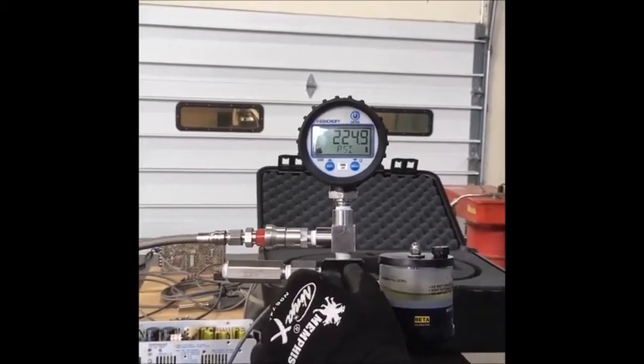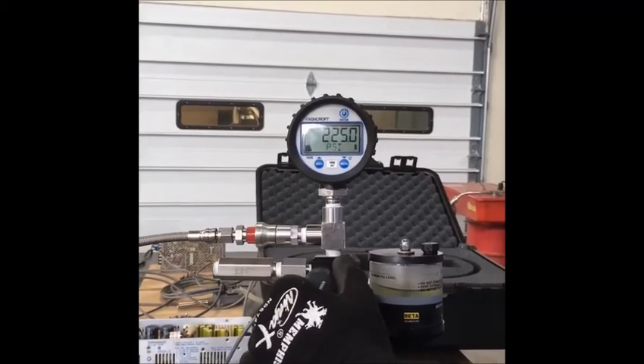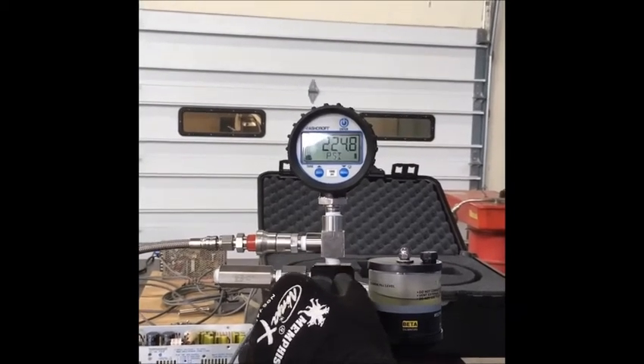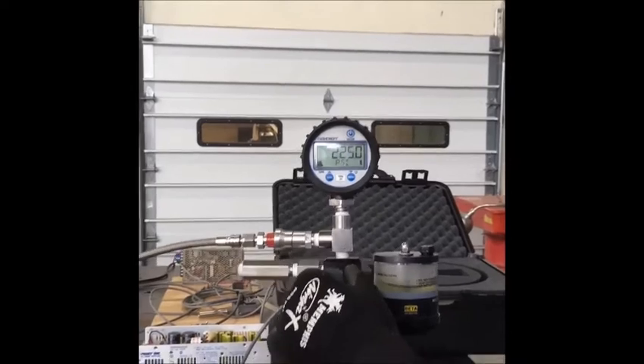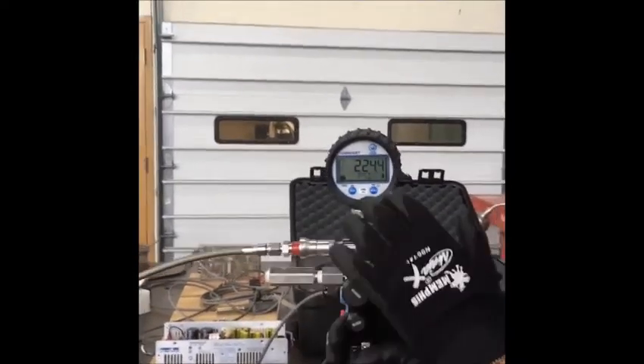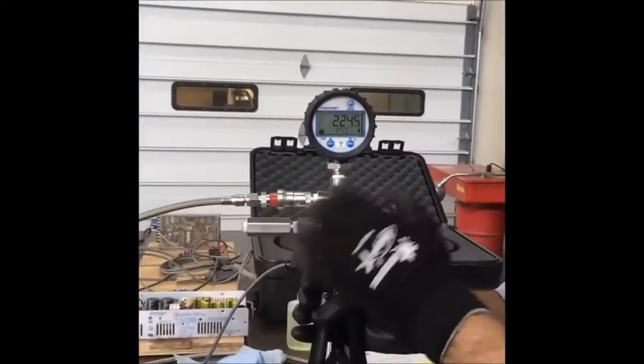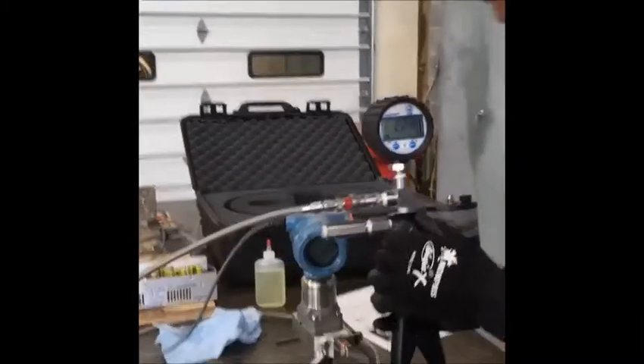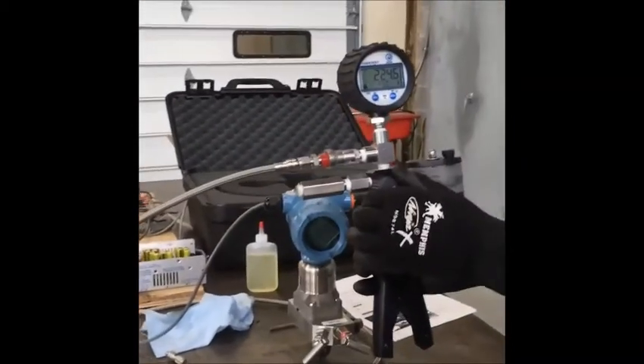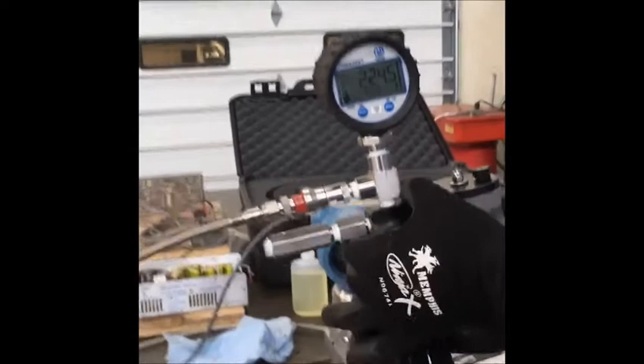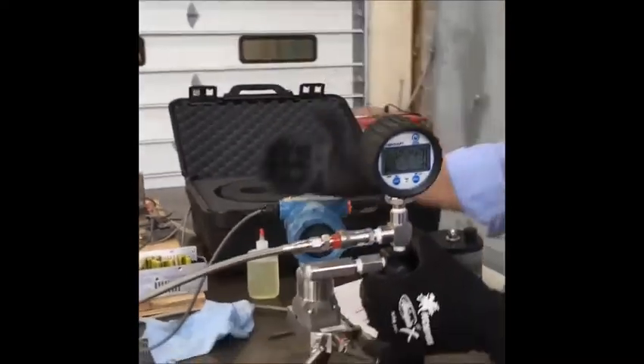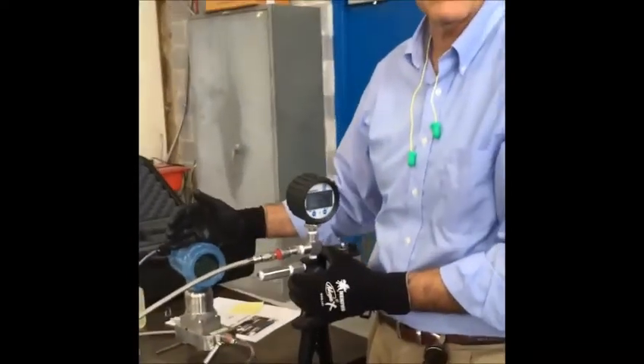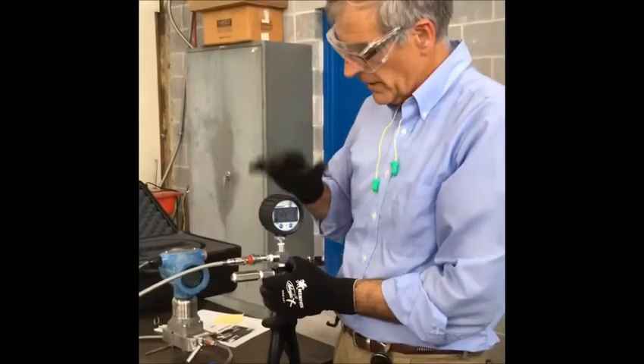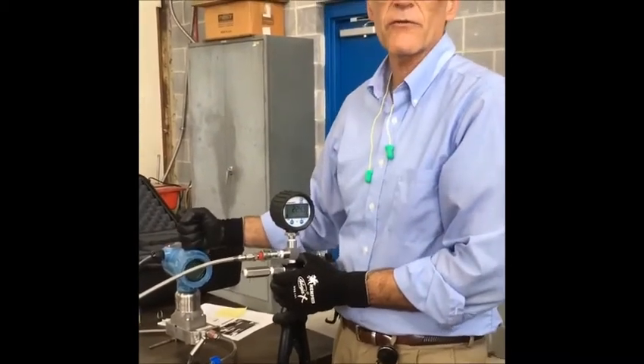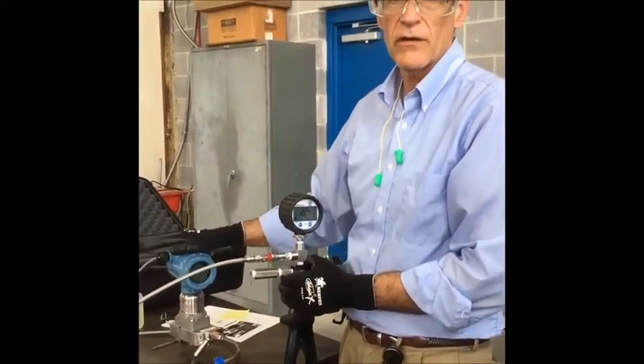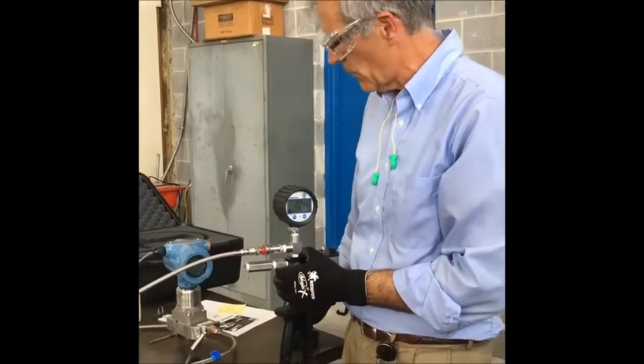Okay, there, just right about at the set point, or I'm jumping around it just a little bit. Pretty close. But the intent of this is when I reach the cutout set point on my calibration pump, I should also reach it on my transducer, and the machine better cut off. So you're sitting here, this would really be a control panel in the real engine room. Once I hit my cutout set point, I need to hear that compressor stop. That's a requirement of the code to prove that the high pressure cutout works.